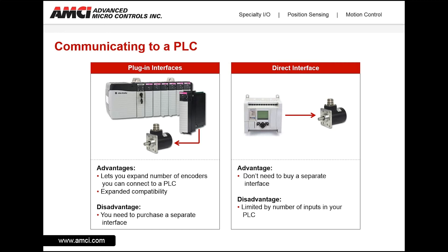There's also a direct interface, which takes advantage of the inputs or interfaces available directly on the PLC, such as analog inputs built into the PLC or a networked interface. The advantage is you don't need to buy a separate interface. The disadvantage is you're limited by the number of inputs — if you only have four analog inputs, you can only bring back four sensors.